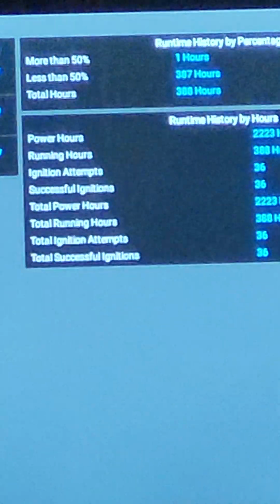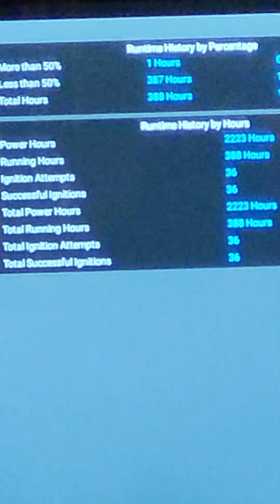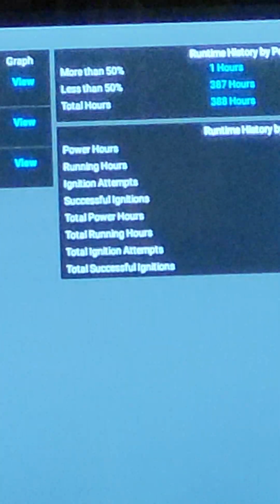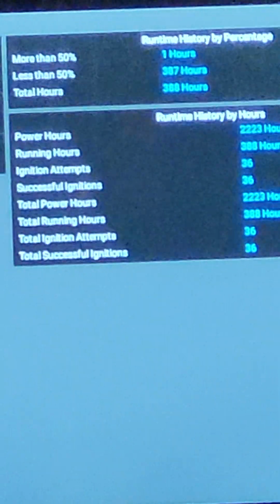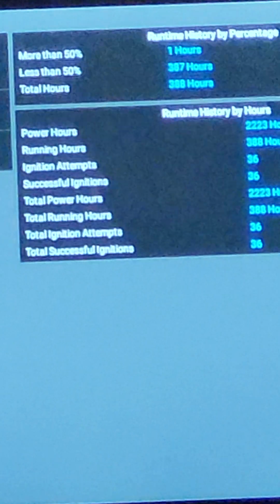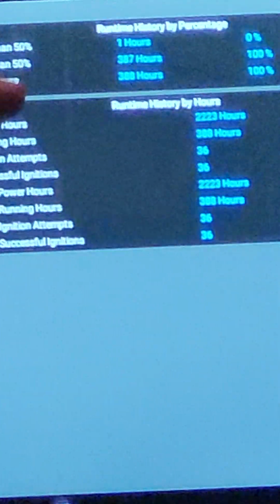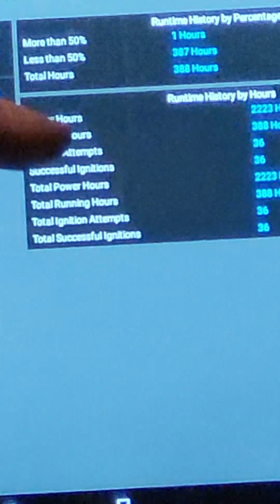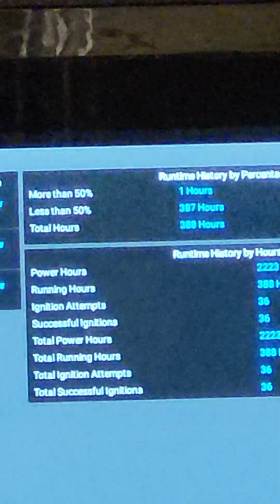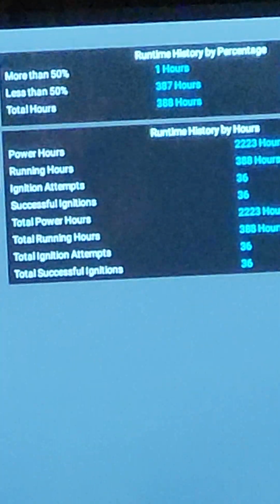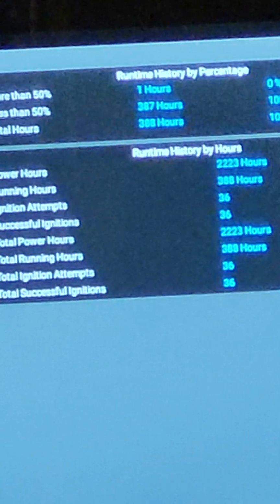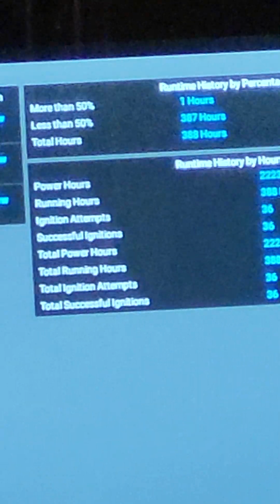Now there's a reset button here. Each year, if you wanted to, you could reset that counter. Now it's not going to reset the total number. The total is there and there's no way you can change it. The only way that changes is by replacing the boards. What would change is the power hours would go to 0, the running hours would go to 0, and then the ignition attempts would drop out. So basically you could see what kind of time you're putting on it, and it would reset the runtime percentage so you can start fresh each season. So just a way to see where the boiler's running or how hard it's running.